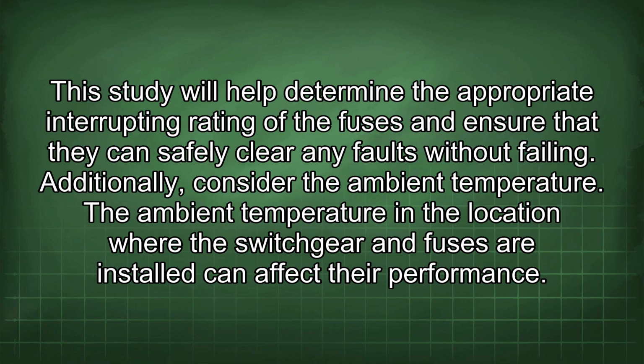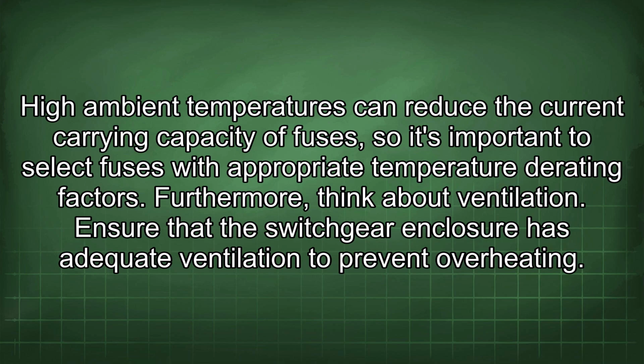The ambient temperature in the location where the switchgear and fuses are installed can affect their performance. High ambient temperatures can reduce the current carrying capacity of fuses, so it's important to select fuses with appropriate temperature derating factors. Furthermore, think about ventilation.